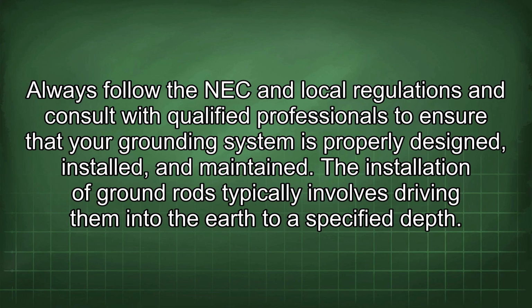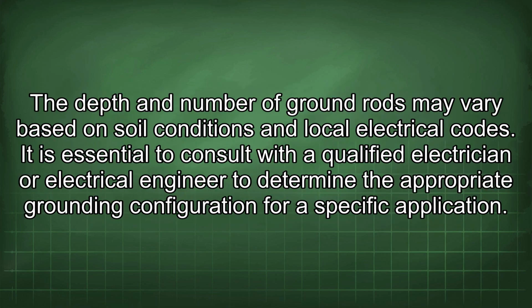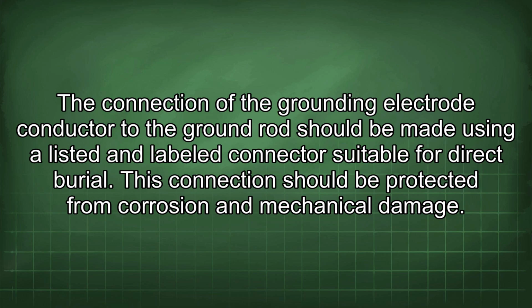designed, installed, and maintained. The installation of ground rods typically involves driving them into the earth to a specified depth. The depth and number of ground rods may vary based on soil conditions and local electrical codes. It is essential to consult with a qualified electrician or electrical engineer to determine the appropriate grounding configuration for a specific application. The connection of the grounding electrode conductor to the ground rod should be made using a listed and labeled connector suitable for direct burial. This connection should be protected from corrosion and mechanical damage.